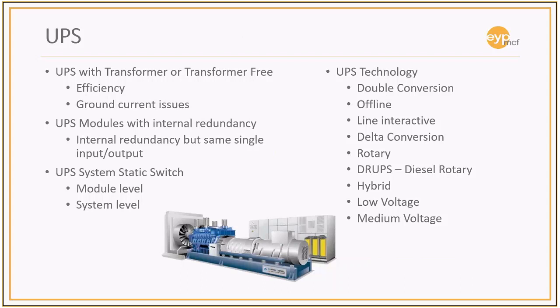Most of these types of systems, whether double conversion or hybrid type environment, can be adapted for any battery type. Typically, if you're going to start with one type of battery, you'd stick with that battery throughout the life. Otherwise, you'll have to make changes to the battery cycles and battery float voltages.